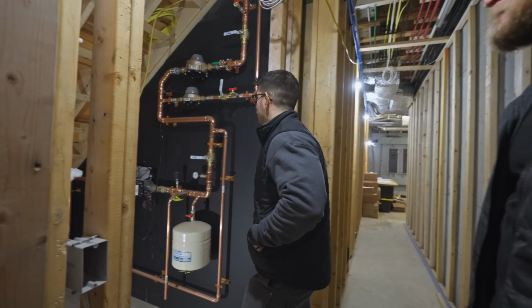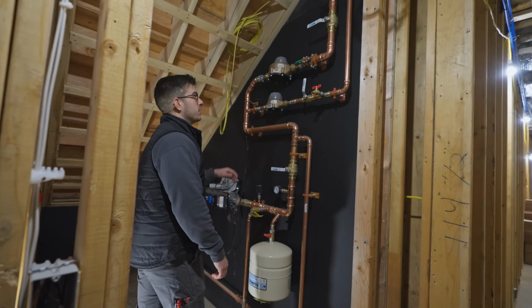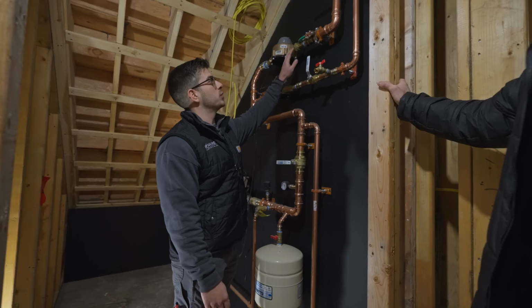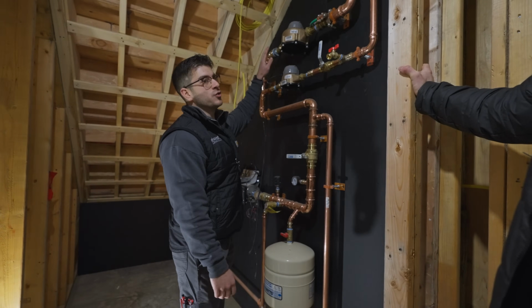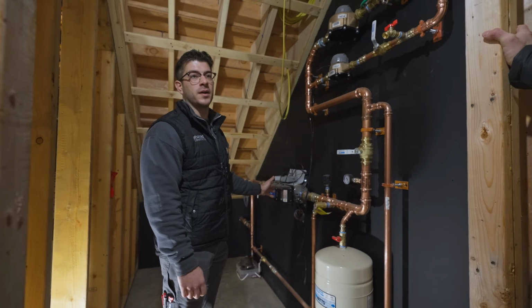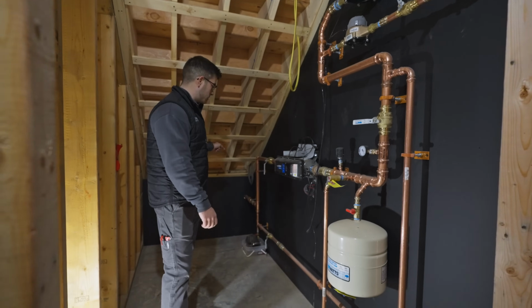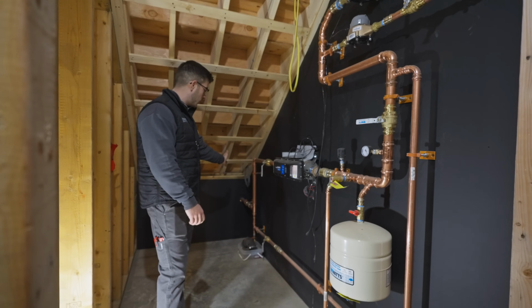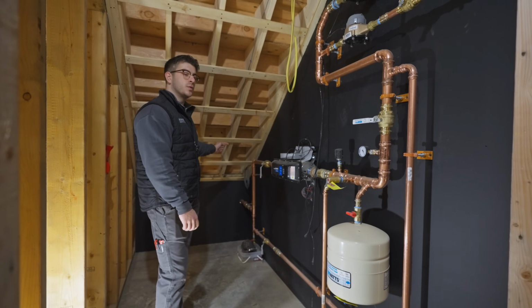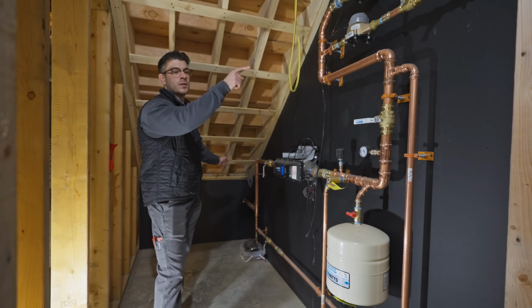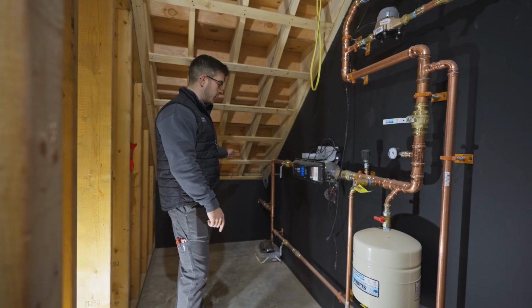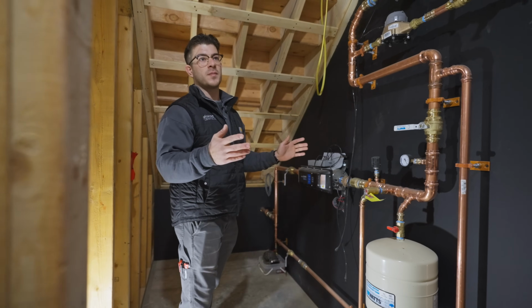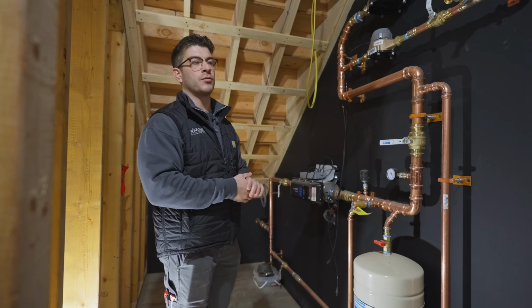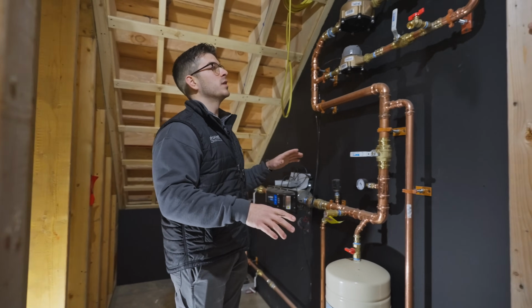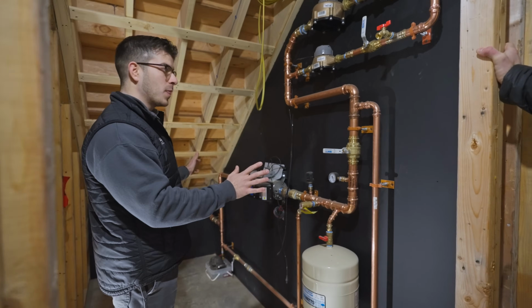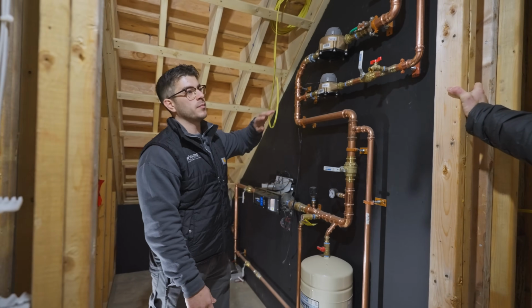We have to ground to the water main coming in, so I needed his meter. Generally what would happen is we jump out the meter—the meter generally comes in directly from where the water main is. So the water main's right under the stairs here. Generally the meter would go right there, and I have to have a continuous line out to my main that's going to ground the beginning and end of the water meter. So if they come and swap that meter out, the bond stays through the cable that jumps out both sides. Here it's a little interesting because you have all this piping before the water meter, so that made it a little tricky for me.